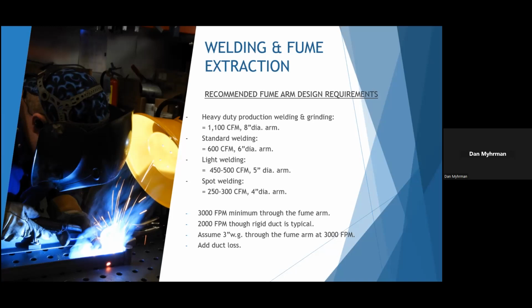For heavy duty production, continuous type welding and grinding, I recommend a minimum of 1,100 CFM through an 8-inch arm, up to about 1,400 CFM. Standard welding, about 600 to 700 CFM through a 6-inch arm. Light welding, intermittent welding, 450 to 500 through a 5-inch arm. Light spot welding, about 250 to 300 CFM through a 4-inch arm. I mentioned 3,000 feet per minute through the fume arm. Once you get up into the ductwork, decrease that down to 2,000 feet per minute.